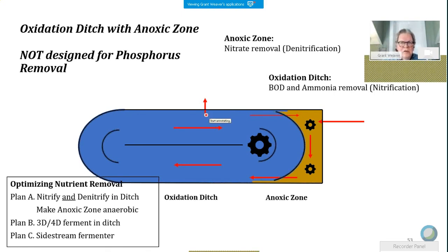I've seen an oxidation ditch in Tennessee where the phosphorus in the ditch was very low, 0.0 something, 0.08. I think they were getting that in the Athens Little Mouse Creek plant. Going into the clarifier and coming out of the clarifier, it was over 1.